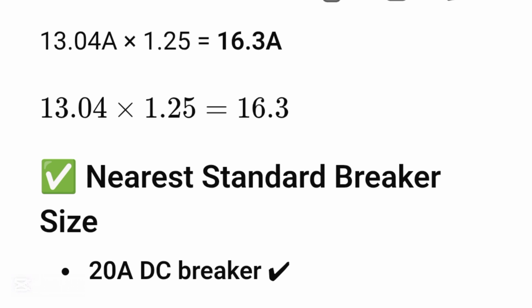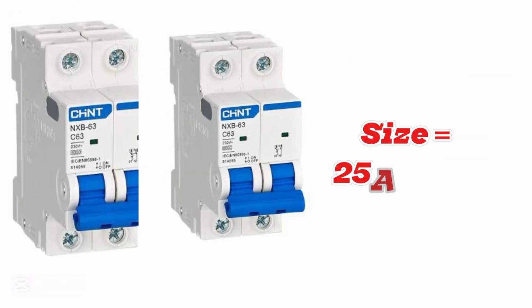Now, if we oversize it by 25%, that will multiply by 1.25, we'll have 16.3 amps. Now, the nearest standard breaker in the market is 20 amps. So that's why we selected 20 amps, which is also below the 25 amps they said is the maximum rating for series fuse. Now let's turn our attention to the AC breakers.